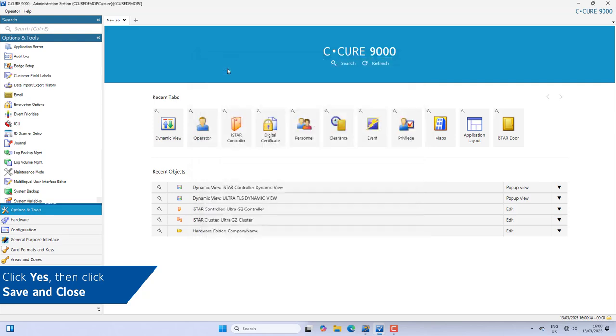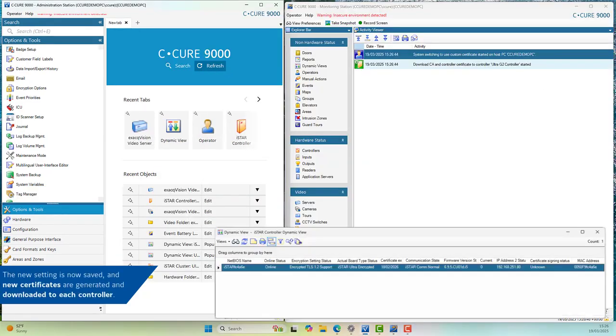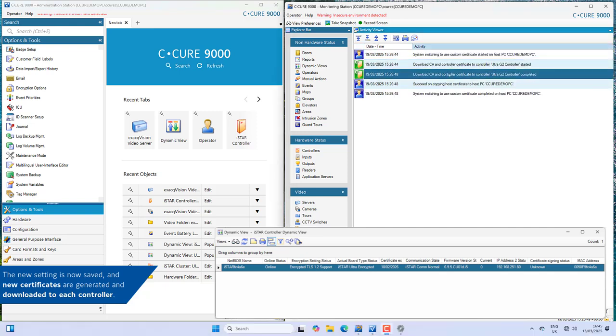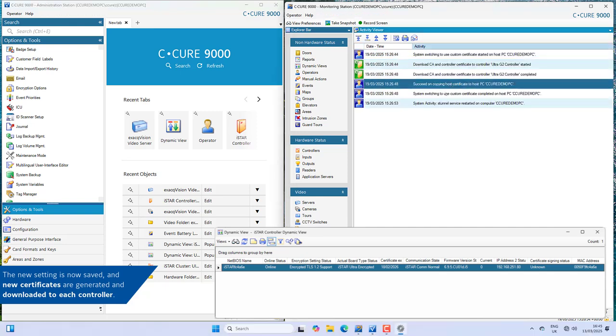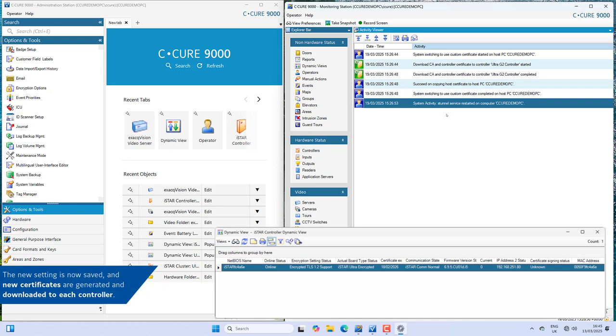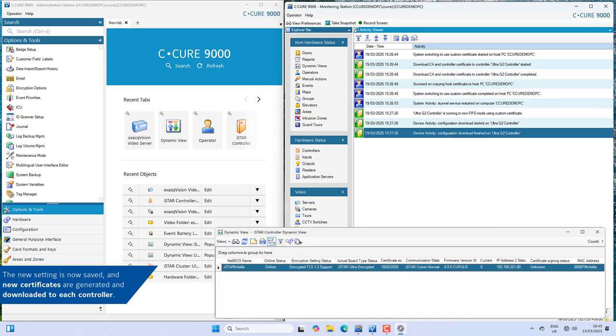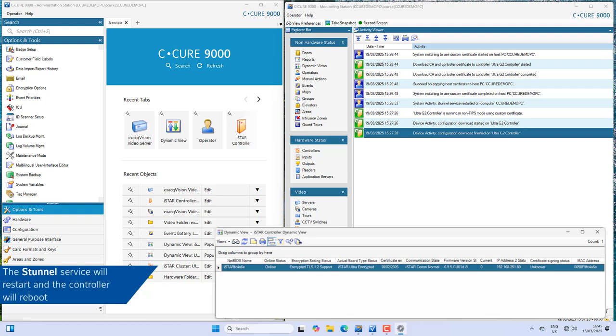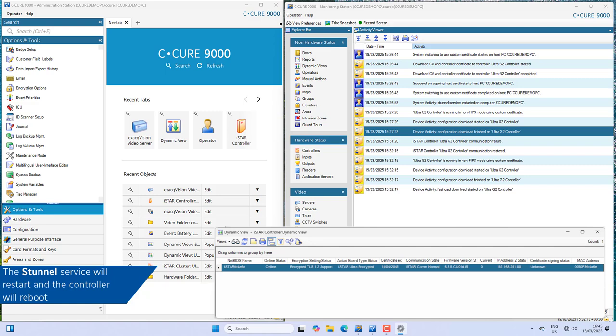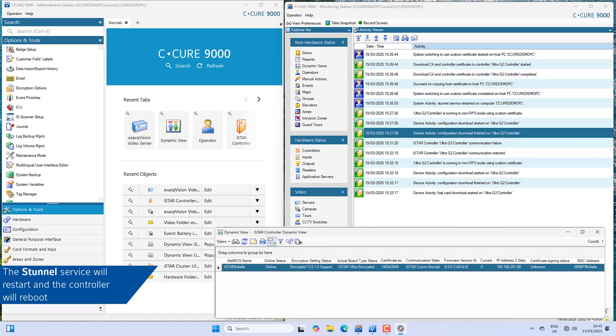Use the Monitoring Station and iStar Dynamic View to verify the new certificate is generated and downloaded to each controller. The messages you will see will vary depending on whether you have selected host-based or controller-based. The S-Tunnel service will be restarted and the controller should reboot. This process could take some time depending on how many controllers you have.